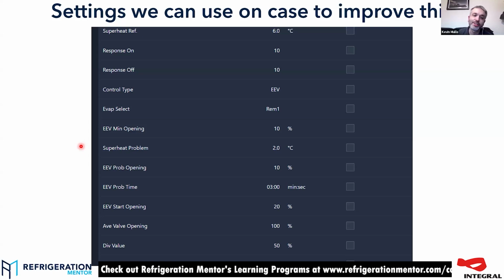With the transducer, most of the time, you can very easily go to a problem opening of 0. All these things are telling you there's a problem with the coil, and it's just a question of how much you need to keep that coil running and doing a little bit if there's a minor problem, or whether you just go, no, rack protection is the key here, so I'm going to shut that valve the moment the superheat looks terrible. And you know your systems better than I do as to what's priority in that regard and what your system can cope with. Again, start opening there is the other key one.